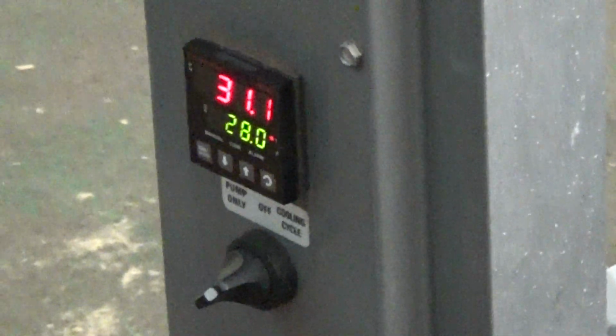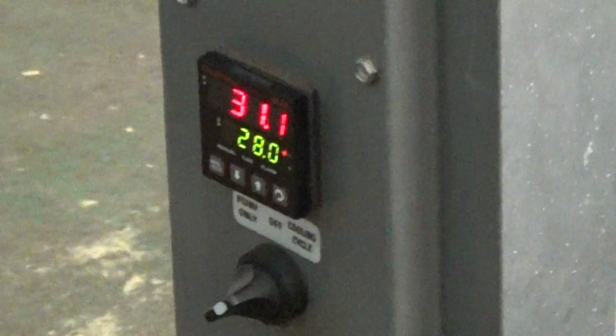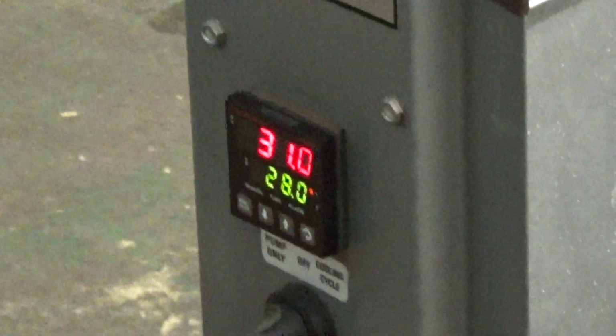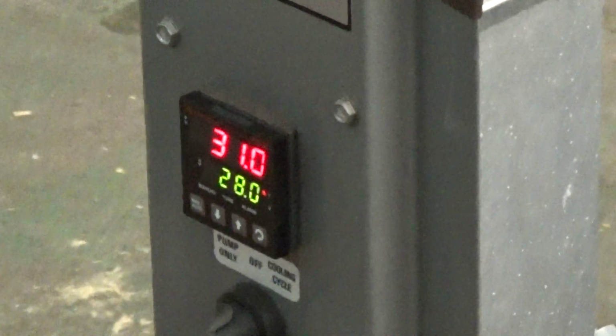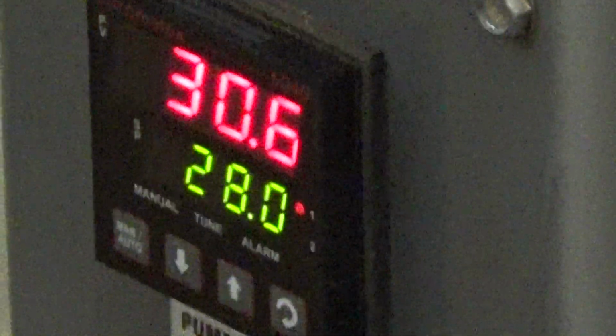And you can hear that the compressor's on, just kicked on. It has a differential of 5 built in, which is pretty normal. So when it gets back up to 30, you can see we're just chilling right now, the compressor turns on. So it's plus 2 degrees, minus 3 from the set point. So this will actually chill down to 25, and that's when the compressor shuts off.